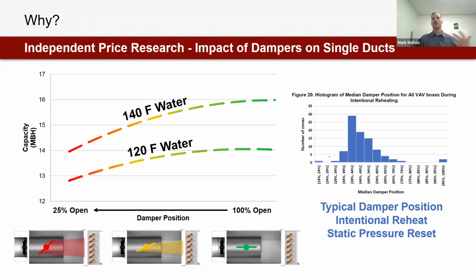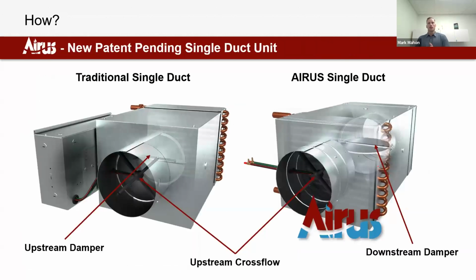But the truth is, even with static pressure reset, we still generally see dampers in fairly closed off positions. This is from an ASHRAE study looking at an office building in California, and they were measuring the typical damper position during intentional reheat with static pressure reset. They still found the bulk of the time, the damper was 40 to 60% open, so in a fairly closed position. So what we've done is we've created a new product.